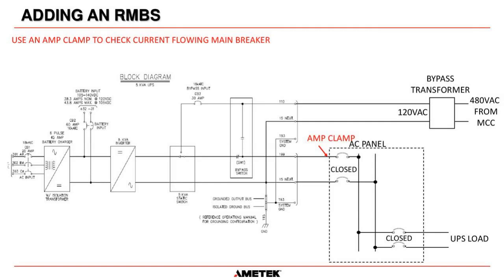What I've done is I've drawn an AC panel here. This is usually what is connected on the output of a UPS system. There's an AC panel which then distributes all of the UPS backed up AC to load circuits. Now, I've only drawn one load circuit on this AC panel, but that's just for ease of viewing this drawing. There's usually going to be multiple loads connected onto that AC panel. And then also remember, this is the main AC input breaker to that AC panel, okay?